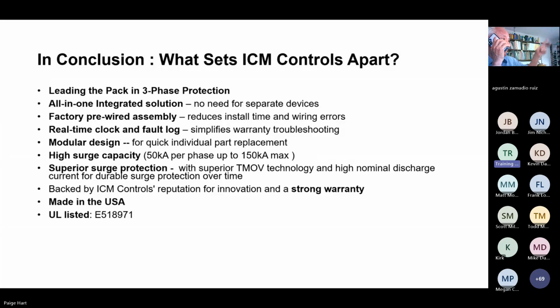Superior surge protection design with the TMOVs in there, which we mentioned are thermally protected metal oxide varistors. Those are your surge elements. They clamp the voltage at the rated voltage of the MOV, and they dissipate the surge portion of the event as heat. If the surge is so big that it overcomes that device, it's not going to sit there and cook or melt or do anything like that. It's going to blow a thermal fuse and take itself safely out of the circuit. Again, superior quality, superior safety, high nominal discharge current for durability. You're going to get a really good surge protector there.